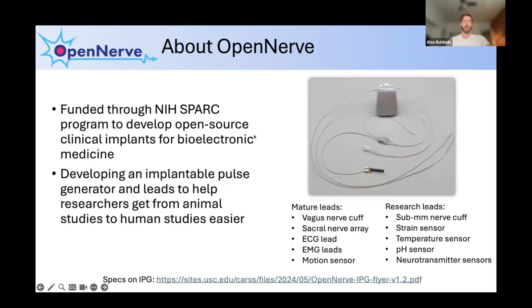OpenNerve is a platform developed by the CARSS Center where I'm working now. It's funded through the NIH, the US government agency that does a lot of medical research here. The mission is to create an open source system for bioelectronic medicine — an implantable device that interacts with nerves that innervate the different organs of the body in order to treat or cure different diseases. What we've made is similar to a traditional implantable pulse generator used for pacemakers or other implantable devices, but more flexible, with more leads, electrodes, or sensors. Different groups in our center are working on stimulation or sensing leads that researchers can use to create closed-loop therapies.